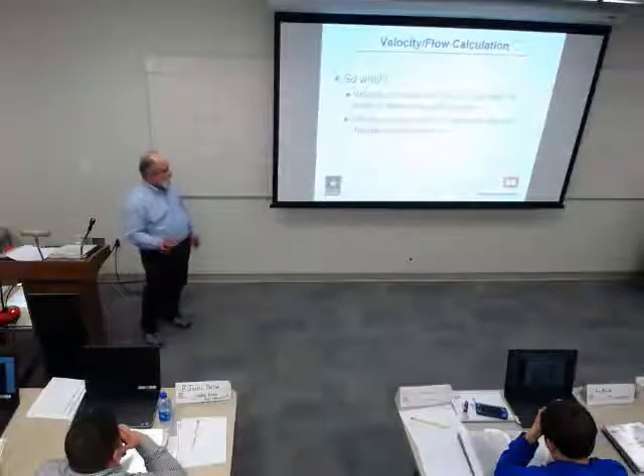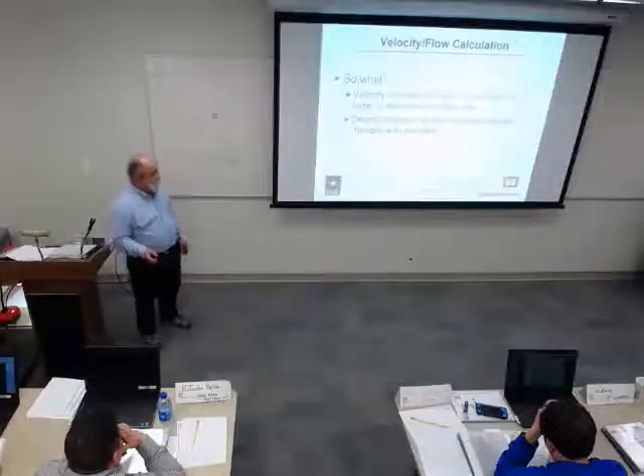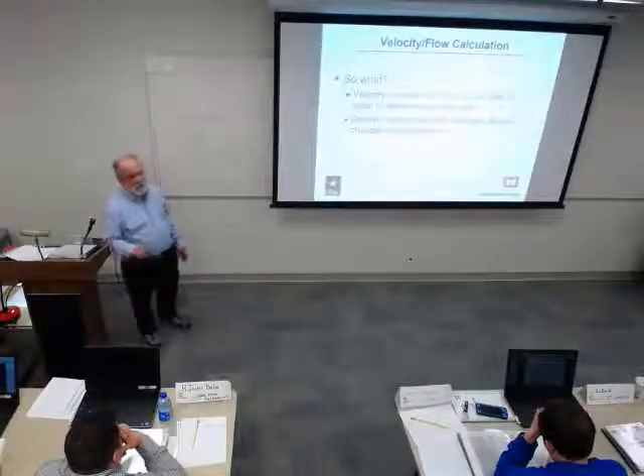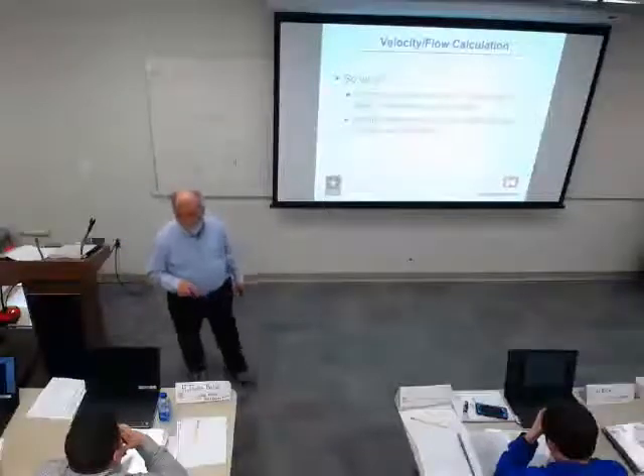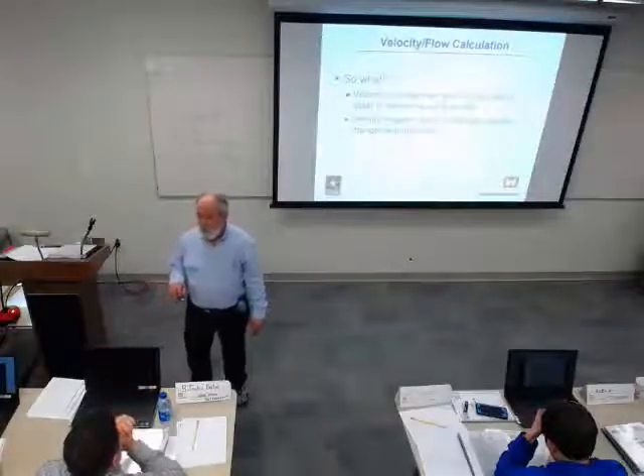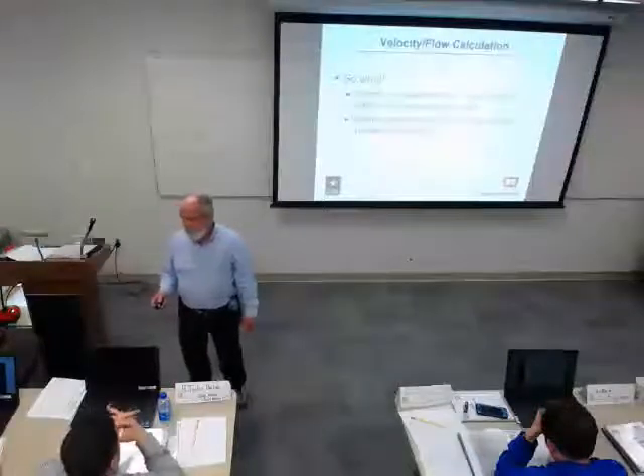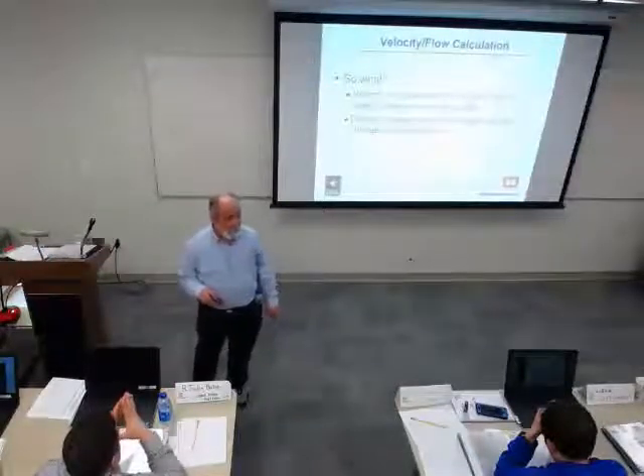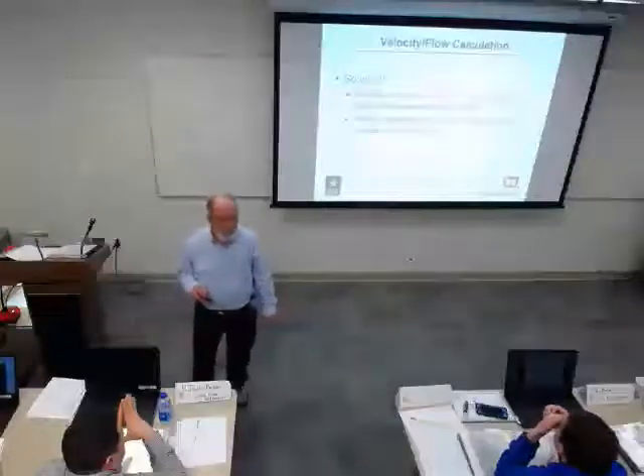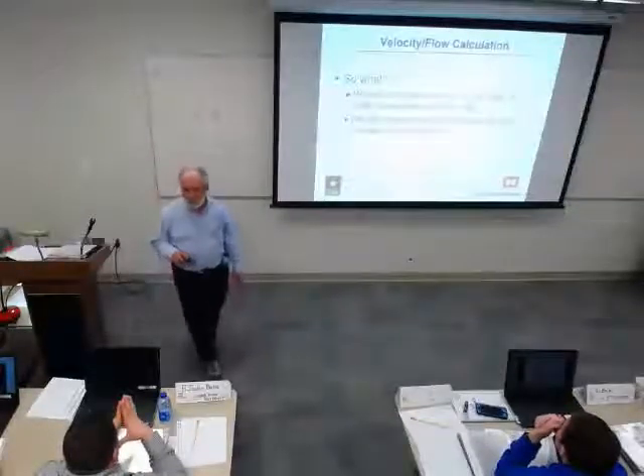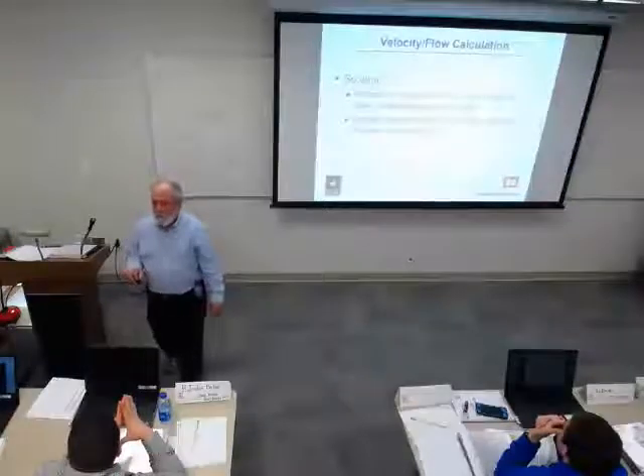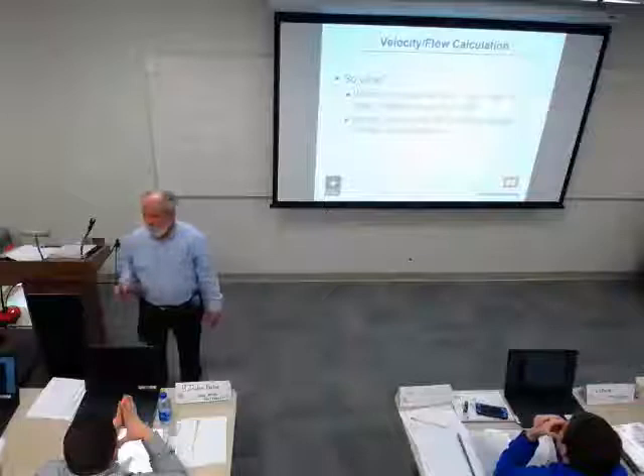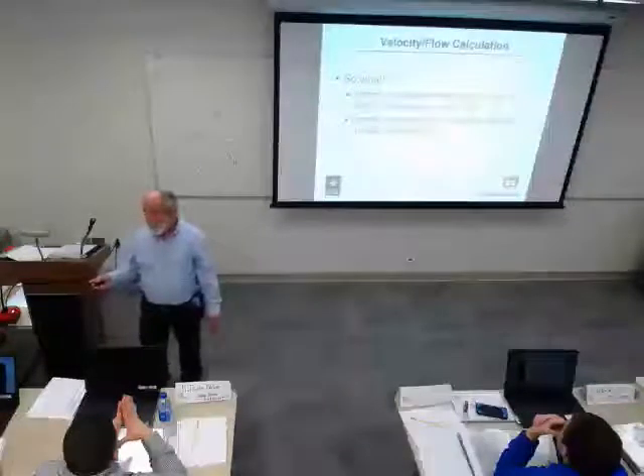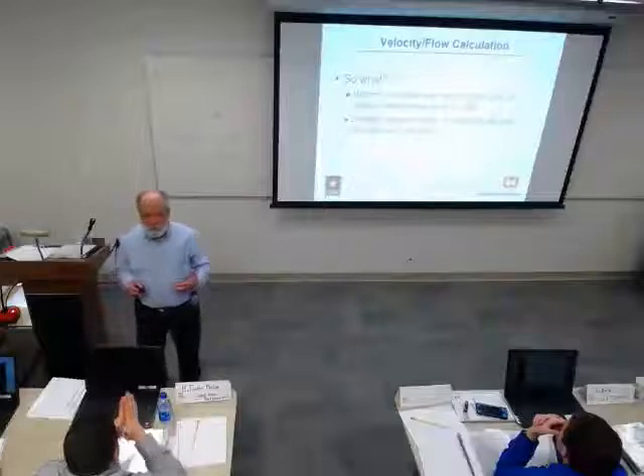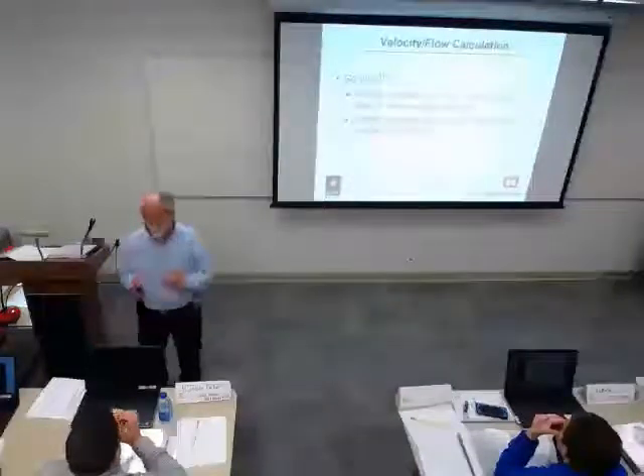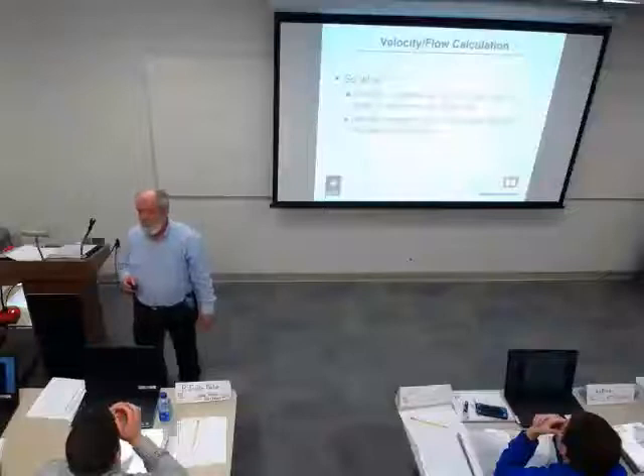So velocity is measured with the pitot tube in order to determine the airflow rate. Density impacts the velocity readings, and it changes with elevation. Most of the equipment that our tab guys use now has ways of correcting for the density. You'll want to check with your tab guy, when he's measuring, whether or not his does and how it does. With a pitot tube, it's a little harder to correct for density without doing the manual crank. The reason is that most of the stuff that measures it is not in the airstream, so it doesn't know what the airstream temperature is.